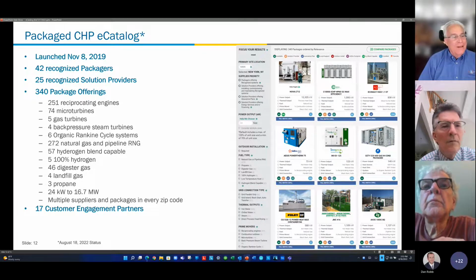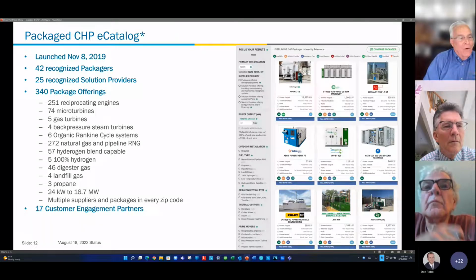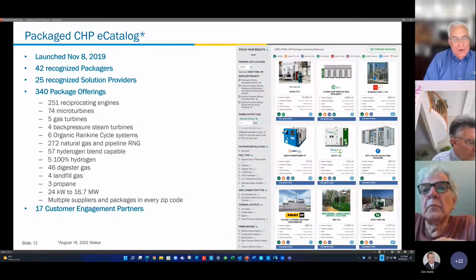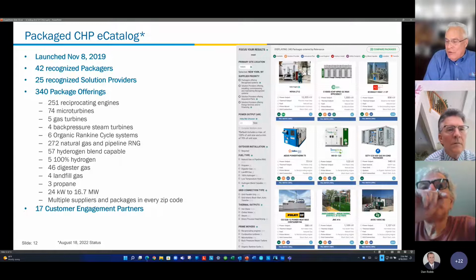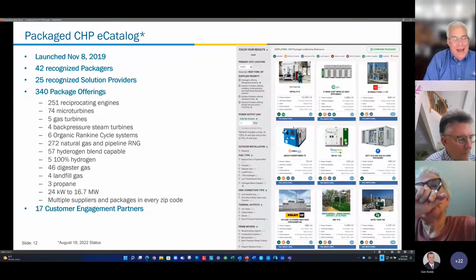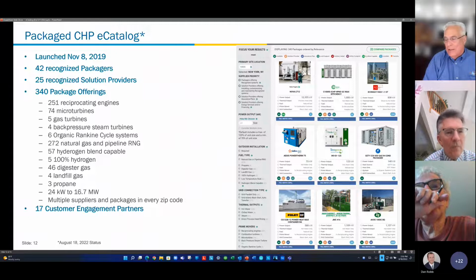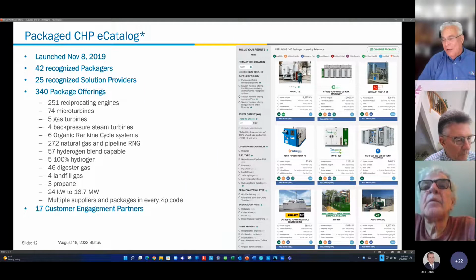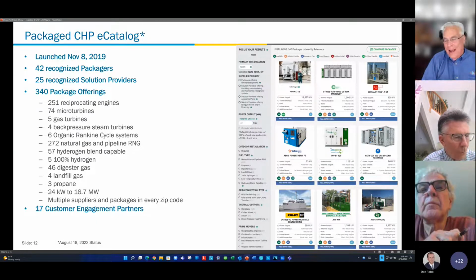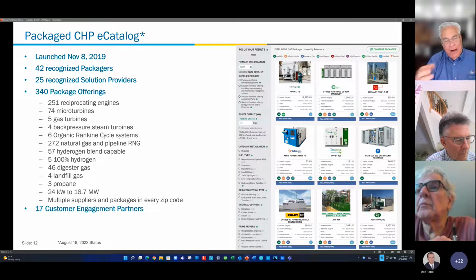We're not only dealing with reciprocating engines, microturbines, and gas turbines, but also back pressure steam turbines—particularly for replacing pressure reducing valves, a great way to save energy and reduce the electric burden on the grid. We've also got organic Rankine cycle systems that use geothermal or waste energy, typically from 1,000 degrees Fahrenheit down to 300 degrees Fahrenheit—a great use of that type of energy.